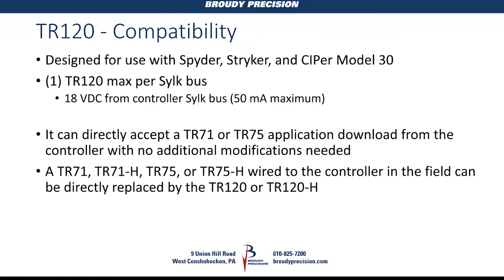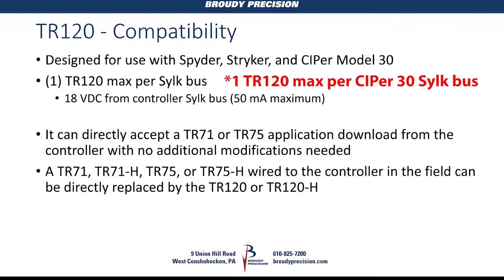Honeywell will likely be updating their spreadsheet for calculating Sylk devices. On the CIPer 30, you can use four TR-120s since they must have a power supply boosting that Sylk bus. The TR-120 is compatible with the Spider PUL/PUB, the Stryker controllers, and the CIPer Model 30.